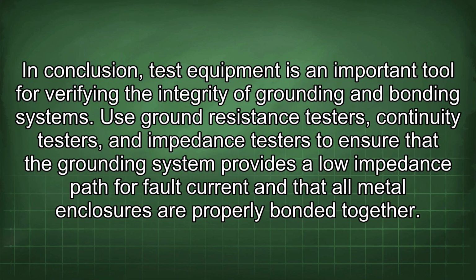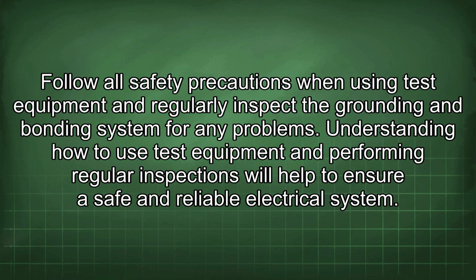In conclusion, test equipment is an important tool for verifying the integrity of grounding and bonding systems. Use ground resistance testers, continuity testers, and impedance testers to ensure that the grounding system provides a low impedance path for fault current and that all metal enclosures are properly bonded together. Follow all safety precautions when using test equipment and regularly inspect the grounding and bonding system for any problems. Understanding how to use test equipment and performing regular inspections will help to ensure a safe and reliable electrical system.